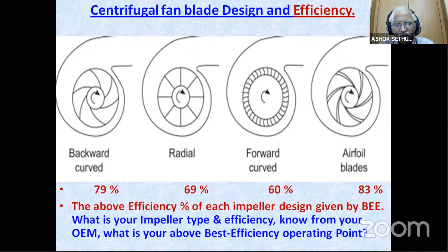So if you see the blowers, backward curved blower, radial blower, forward curved, and airfoil, you can see the percentage of efficiency: 79, 69, 60, and 80. This airfoil type is the best suited for all the AHUs, air handling units, especially in the HVAC segment. In your college, you go and visit your air conditioning installations and check your fans. What is the type of fans? What are the impellers that have been used in your fans, especially in the air handling units?